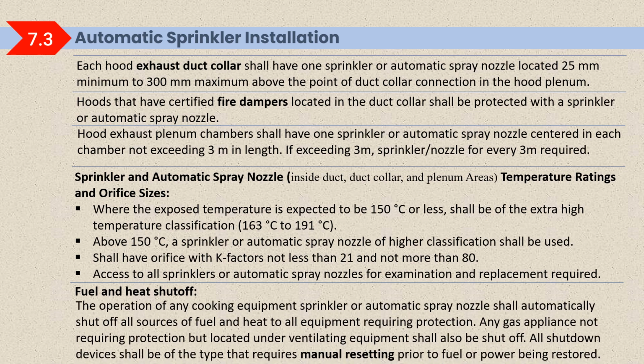Required fuel and heat shut-off. The operation of any cooking equipment, sprinkler or automatic spray nozzle shall automatically shut off all sources of fuel and heat to all equipment requiring protection. Any gas appliances not requiring protection but located under ventilating equipment shall also be shut off. Also, shutdown devices shall be of the type that requires manual resetting prior to fuel or power being restored. So once it is shut down, it can only be restarted by manually resetting that. So this type of provision is required.